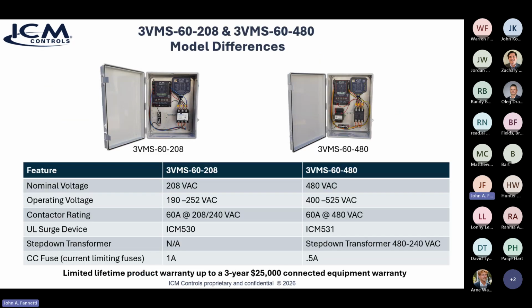All right, so which one do you choose? We have two different models. But which one do I need? Well, really, it comes down to the voltage that you're using. If your nominal voltage is 208, then you've got to have the 3VMS-60-208. Now, that's limited to a 60 amp rating. When I say limited, that's really a very good rating, because that's right in the bulk of where you're going to see your most usage. We've done some studies on this, and yes, are there applications that go a little higher than 60 amps? Sure, there are, but they're a lot less prevalent. Most of your applications are going to be 60 amps or under. So the 60 amp contactor in there is well suited to handle those inductive loads.